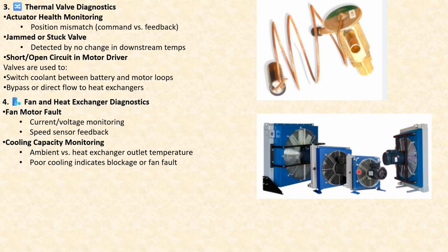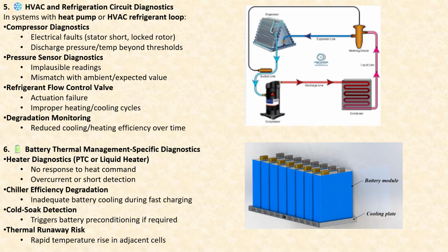All right. So to proceed further, when it comes to HVAC and refrigeration circuit diagnostics, in systems with a heat pump or HVAC refrigeration loop, the first big component that comes under diagnostics is the compressor. Within the compressor, electric faults like stator short and locked rotor may occur. And when it comes to discharge pressure, temperature beyond thresholds. Now, coming to the pressure sensor diagnostics: implausible readings, mismatch with ambient and expected value.